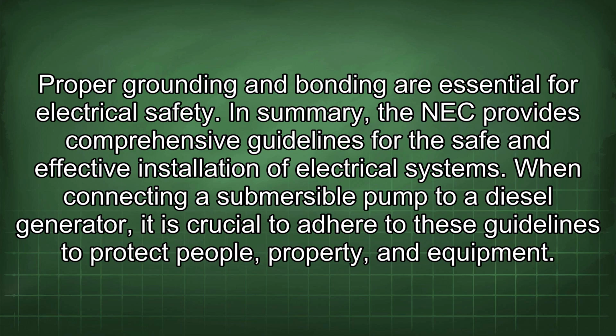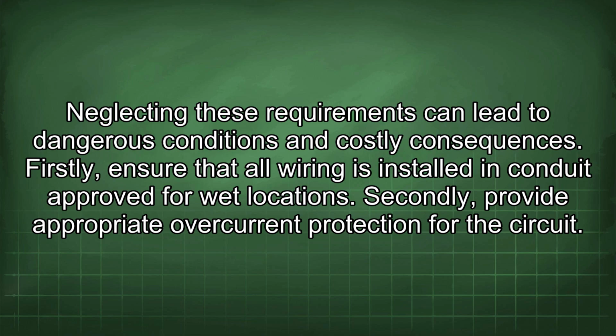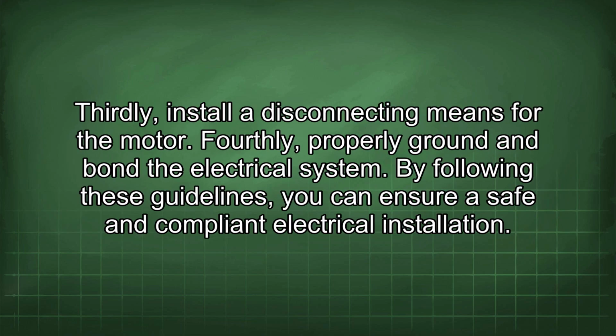In summary, the NEC provides comprehensive guidelines for the safe and effective installation of electrical systems. When connecting a submersible pump to a diesel generator, it is crucial to adhere to these guidelines to protect people, property, and equipment. Neglecting these requirements can lead to dangerous conditions and costly consequences. Firstly, ensure that all wiring is installed in conduit approved for wet locations. Secondly, provide appropriate overcurrent protection for the circuit. Thirdly, install a disconnecting means for the motor. Fourthly, properly ground and bond the electrical system. By following these guidelines, you can ensure a safe and compliant electrical installation.